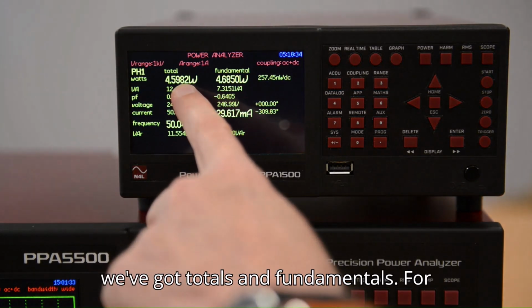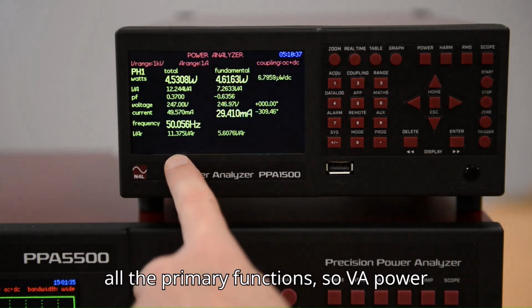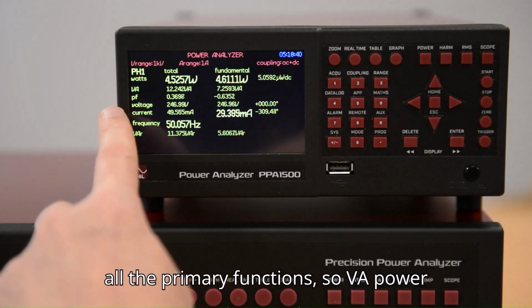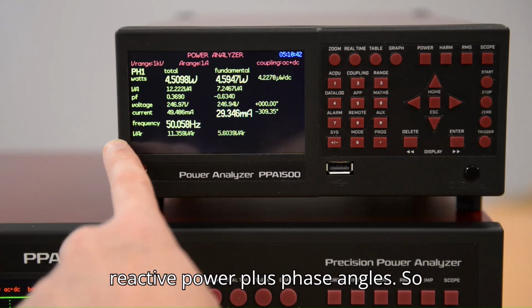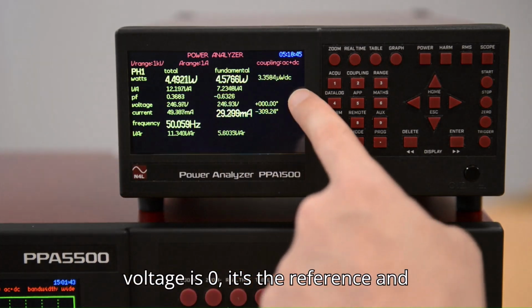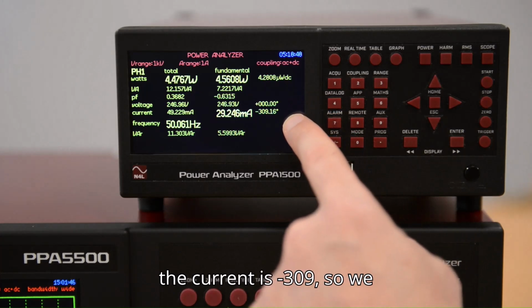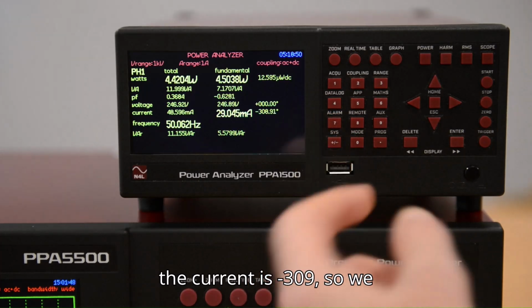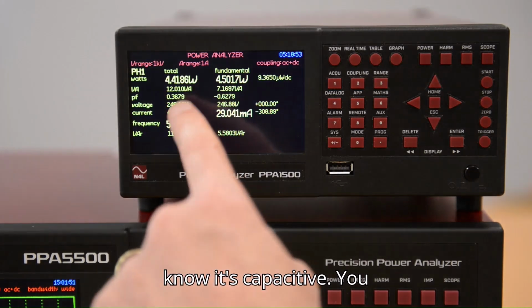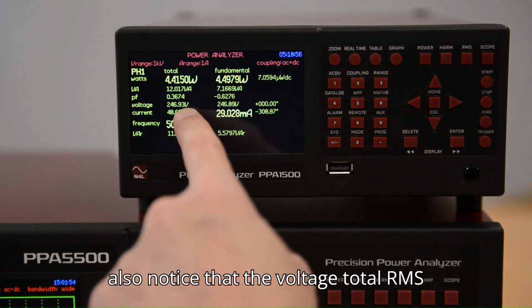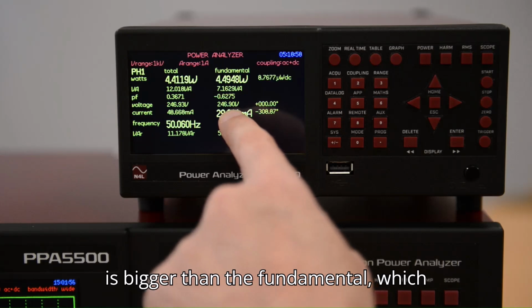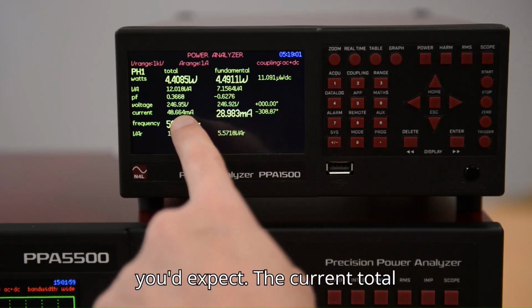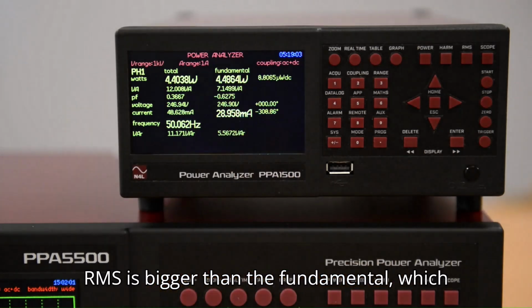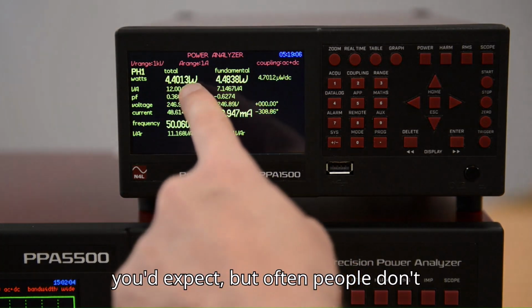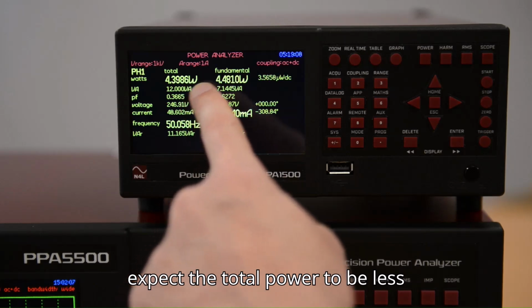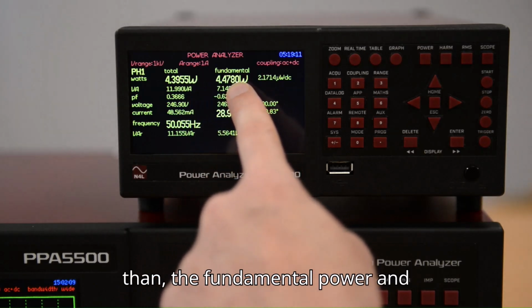And you can see that we've got totals and fundamentals for all the primary functions, so VA, power factor, voltage, current, frequency, and reactive power, plus phase angles. So voltage is 0, it's the reference, and the current is minus 309, so we know it's capacitive. You also notice that the voltage total RMS is bigger than the fundamental, which you'd expect. The current total RMS is bigger than the fundamental, which you'd expect. But often people don't expect the total power to be less than the fundamental power.